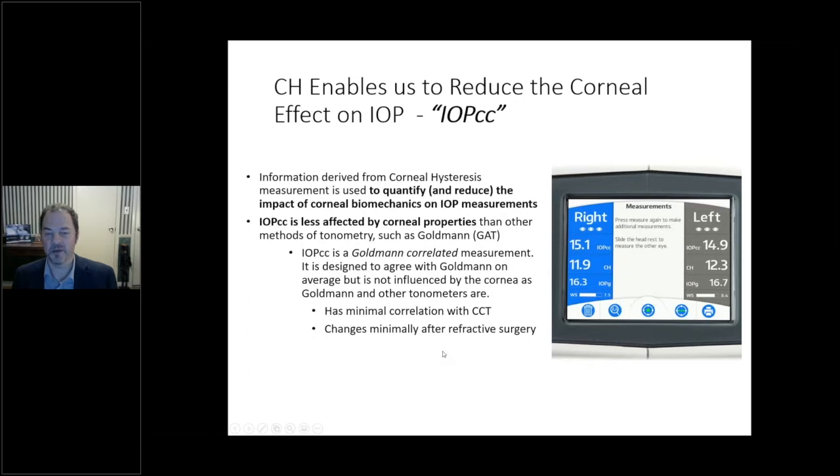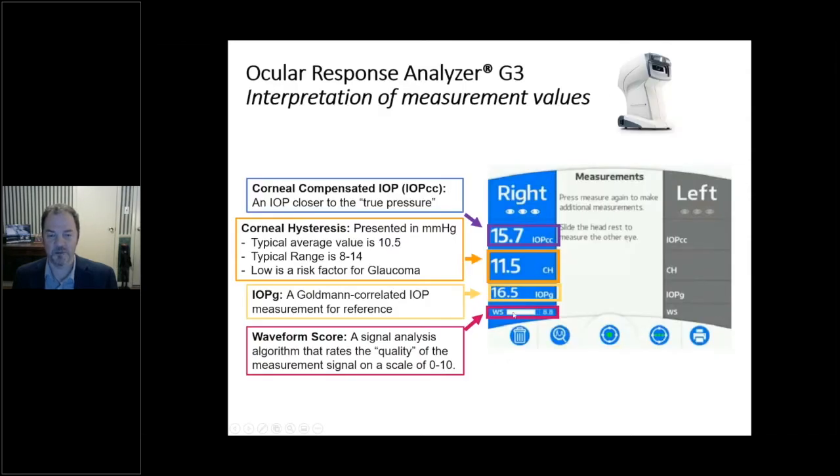On the instrument screen, at the bottom is the waveform score — similar to a signal quality score on OCT. We display a Goldmann-correlated IOP for reference, the IOPcc at the top, and the all-important corneal hysteresis measurement in the middle. The units are millimeters of mercury; an average value is about 10.5, and a typical range in a normal population is about 8 to 14. Low corneal hysteresis is a risk factor for glaucoma; high hysteresis is a good thing — just for reference when we start discussing numbers later.